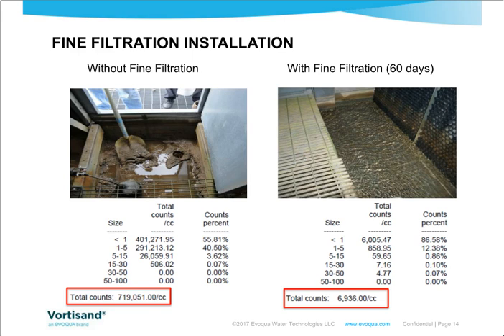Not only is this an improvement in clarity and in quality, but we're also able to now remove the maintenance associated with having to clean out that basin of that cooling tower. You can see here the TSS and the settling in the basin got so bad that they had to shovel out that basin, leading to high labor, high operating costs, having to shut down that cooling tower to get the material out, not to mention the exposure to human health and exposure to potential Legionella.